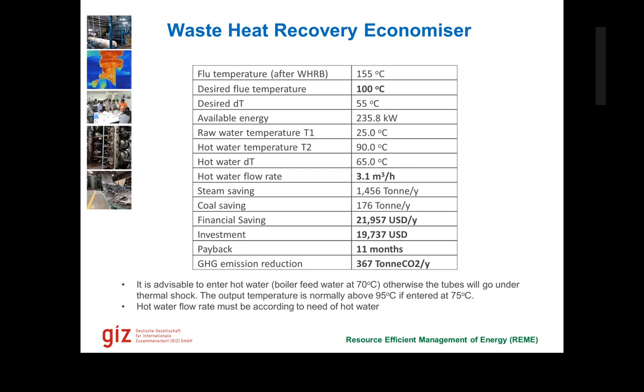Then we can install a normal economizer, which can bring it down to around 100 degrees Celsius, or we can install a condensing economizer, which is more expensive, but then it can bring it down to 60 degrees Celsius or 50 degrees Celsius. This means intentionally doing condensing in the system, recovering carbonic or whatever acid can be produced depending on our fuel intake. So in the case of natural gas, we get carbonic acid. This carbonic acid can be used in the ETP for the neutralization process. So we bring in savings not only by recovering energy, but also through reduced chemicals in the effluent treatment plant.